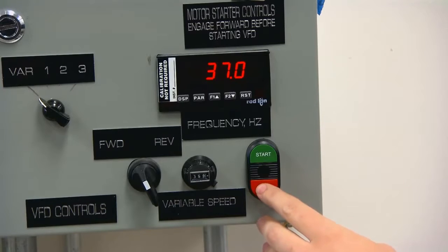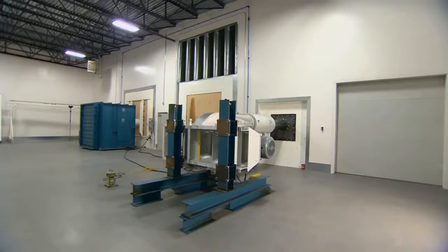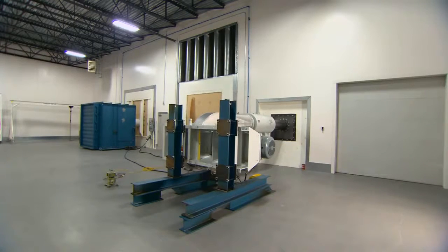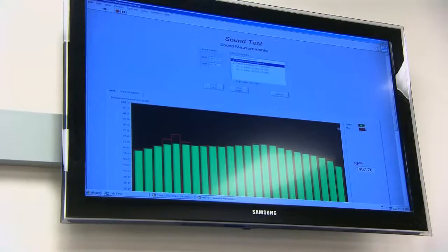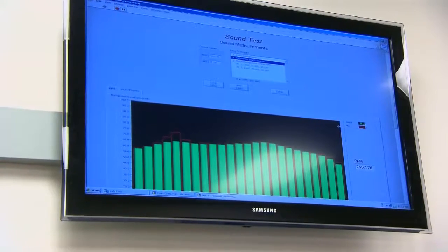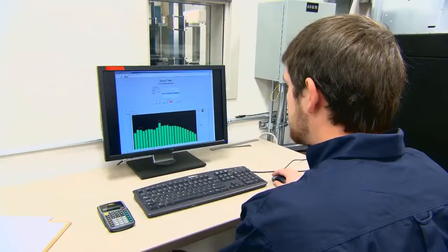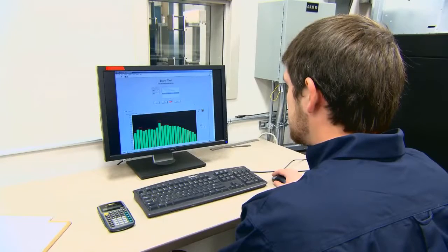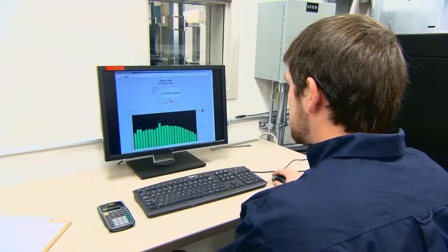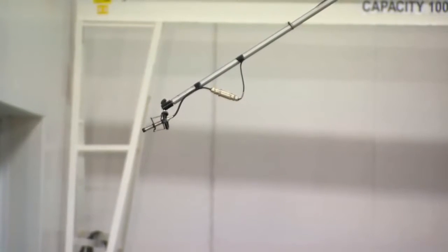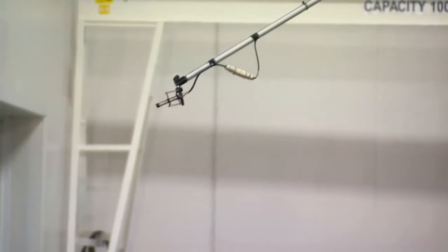So once you determine the sound power level of a test fan, we take it and post-process the data in our engineering tools. We bring in multiple tests into that tool so that we can do further post-processing and analysis to see what are the frequencies at which the sound level is high.